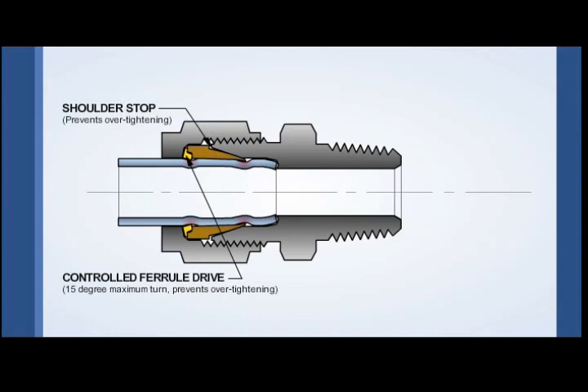With other designs, over-tightening forces the tubing to bulge outward and push the body outwards against the nut, causing severe tube stick and making a fitting remake impossible.